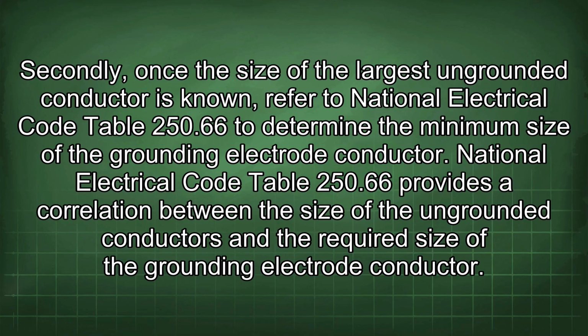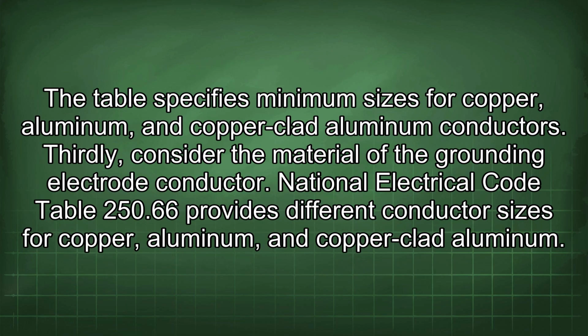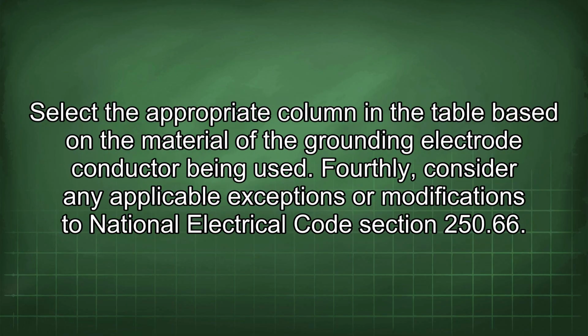National Electrical Code Table 250.66 provides a correlation between the size of the ungrounded conductors and the required size of the grounding electrode conductor. The table specifies minimum sizes for copper, aluminum, and copper-clad aluminum conductors. Thirdly, consider the material of the grounding electrode conductor. Table 250.66 provides different conductor sizes for copper, aluminum, and copper-clad aluminum. Select the appropriate column in the table based on the material of the grounding electrode conductor being used.